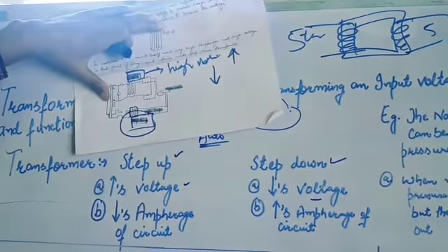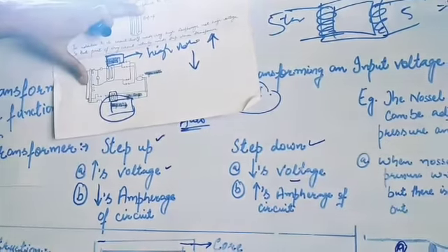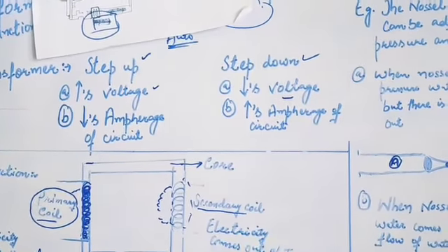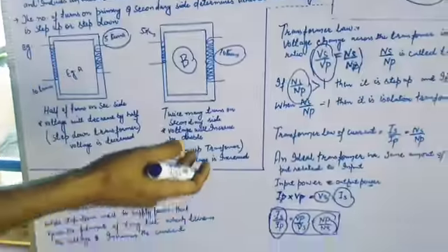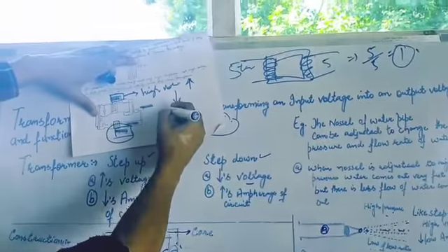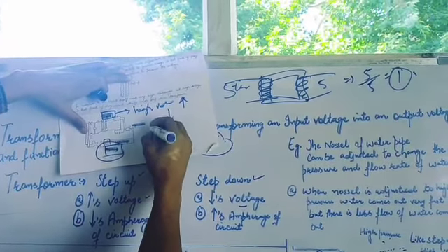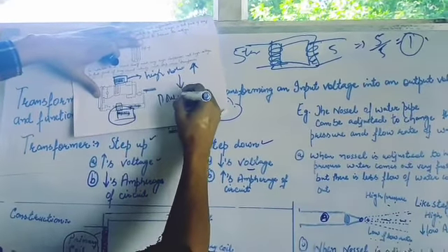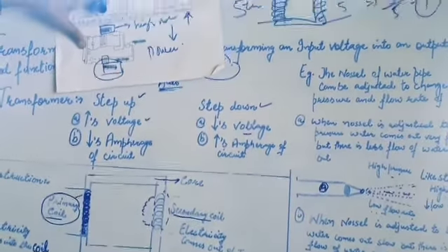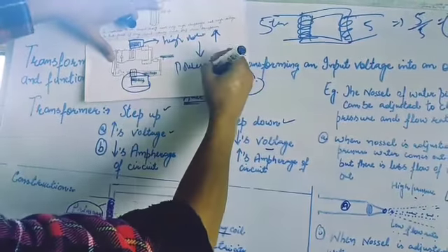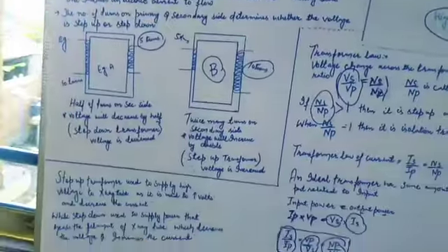Other parts of the X-ray circuit need a step down transformer. The step down transformer is used to supply the power that heats the filament of the X-ray tube, which decreases the voltage, but it increases the current.